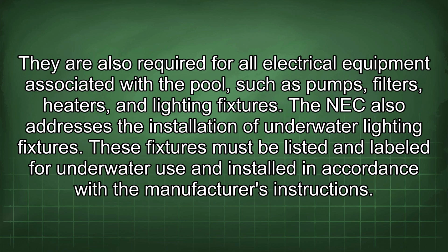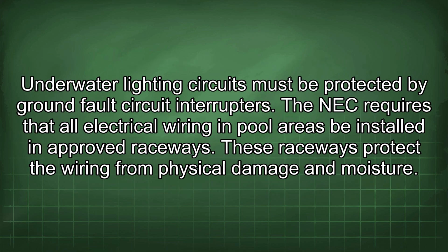They are also required for all electrical equipment associated with the pool, such as pumps, filters, heaters, and lighting fixtures. The NEC also addresses the installation of underwater lighting fixtures. These fixtures must be listed and labeled for underwater use and installed in accordance with the manufacturer's instructions. Underwater lighting circuits must be protected by ground fault circuit interrupters.